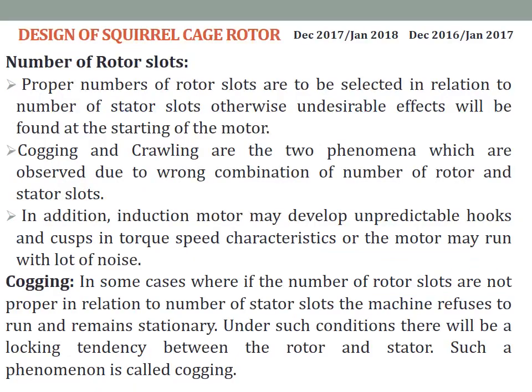Now coming to design of squirrel cage rotor. First we will consider the number of rotor slots. How to select the number of rotor slots. Proper number of rotor slots are to be selected in relation to the number of stator slots. Stator slots we have already calculated. Otherwise, undesirable effects will be found at the starting of the motor.